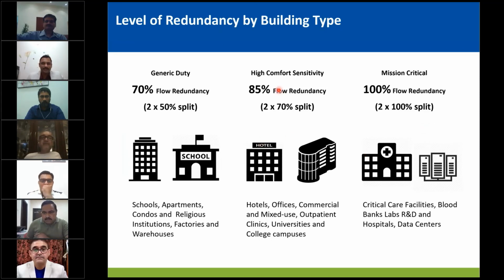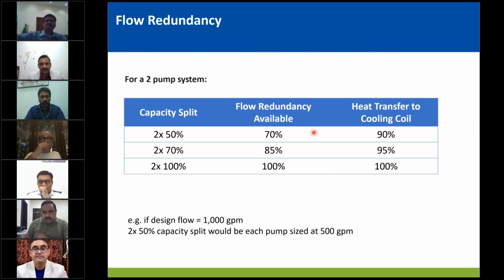So based on the building requirements, not only the flow, but we should look at the heat transfer. If you can get 90%, and if the building doesn't need more than 90% cooling, then you could go for 2 into 50% split. If it needs slightly more, 95%, then you can go to the 2 into 70% split capacity.